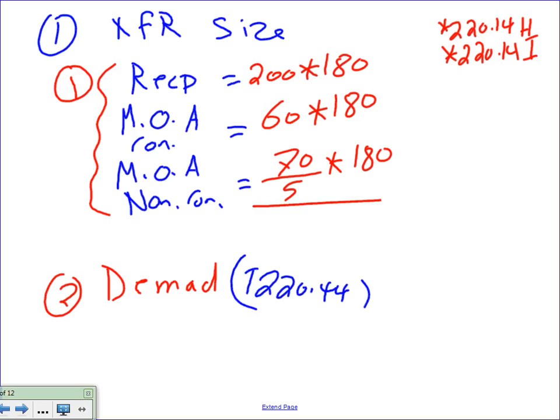And then when you're done, make sure you add them up. And that will end up with 49,320 volt-amps. Any question, guys, about this? Straightforward. That's a calculation that you have to do from 220.14(H) and (I). We did these in the fall, if you remember that. I know the fall was a long time ago. H is multi-outlet assembly and I is receptacles. Please correct me if I did the math wrong.